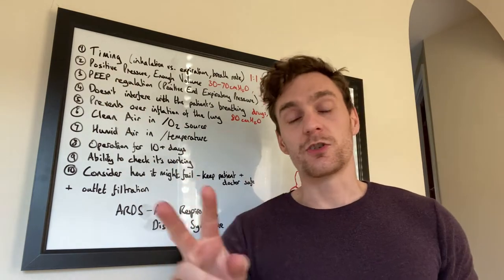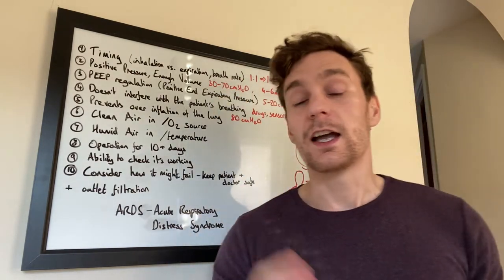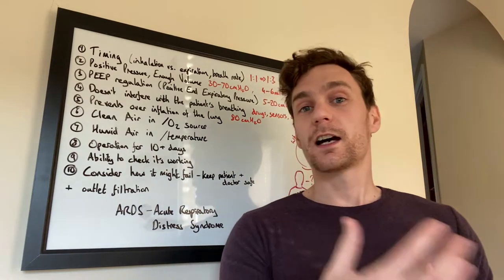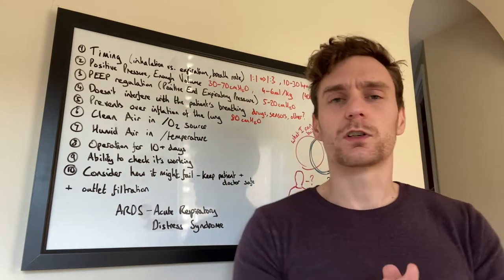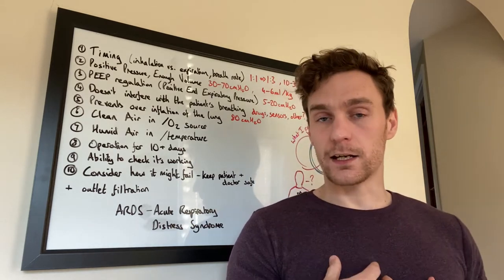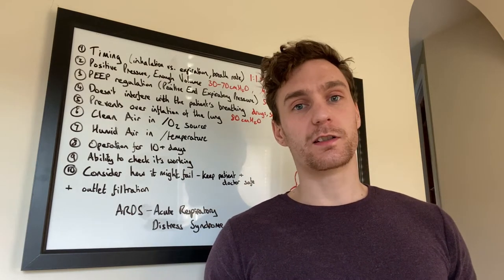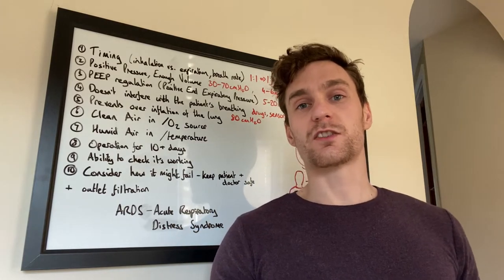Number one: timing. There are two key aspects — inhalation-to-expiration ratio and breath rate. The inhalation-to-expiration ratio could be one-to-one or up to one-to-three — meaning you breathe out for up to three times as long as you breathe in. Breathing rate could be anywhere from 10 to 30 breaths per minute. Different patients have different requirements, and the clinician will want to tune these according to the patient's specific needs.